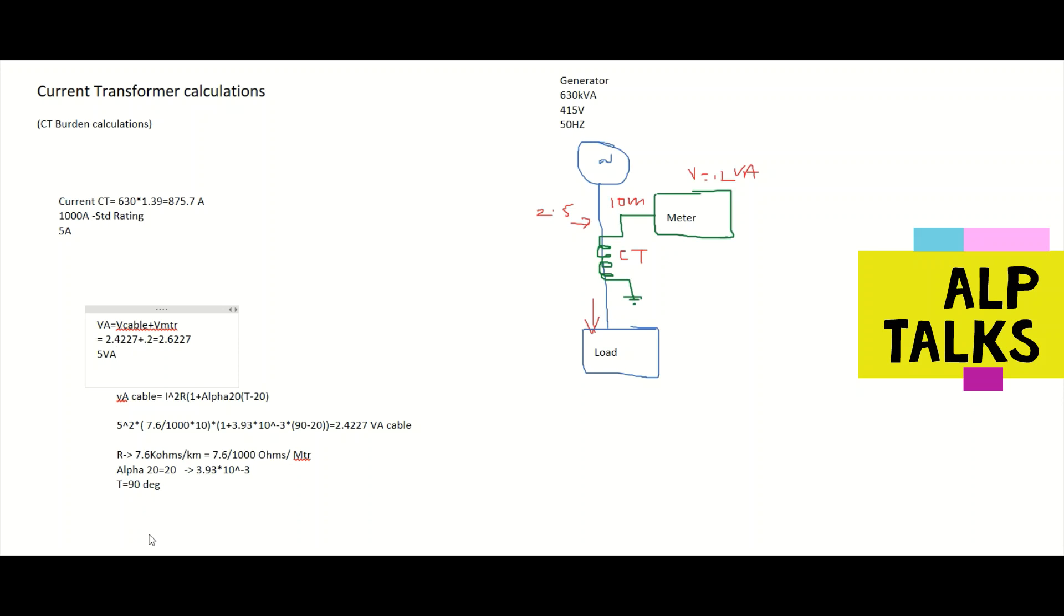So what is the specification? Whatever the CT is there, CT specification, let's summarize it. 1000 amp by 5, this is the ampere rating. Burden is 5 VA. This is by considering 10 meter cable.